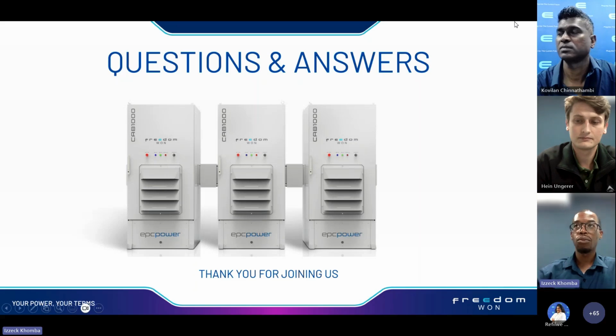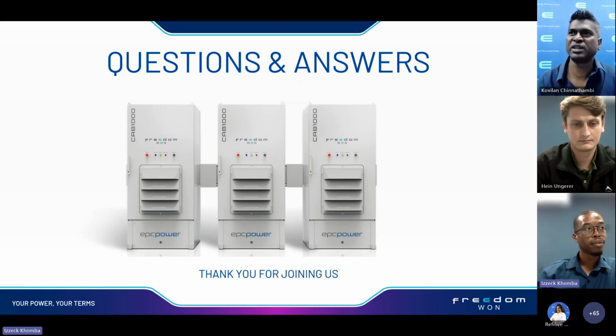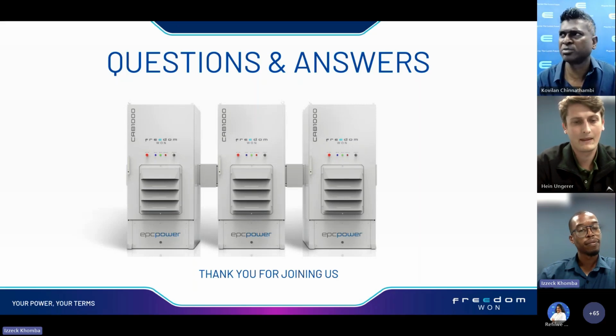Yeah, just to add on to that, it's important to understand that when the inverter is sized correctly, as long as the transient load spike doesn't exceed the inverter rated capacity, it should be able to recover without any issues. So it's very important to do a load study to understand the characteristics of the load in order to determine the correct sizing of the inverter. So in theory, what you're saying is, if it's a 1.4 megawatt inverter, it can supply reactive loads up to its rated capacity.